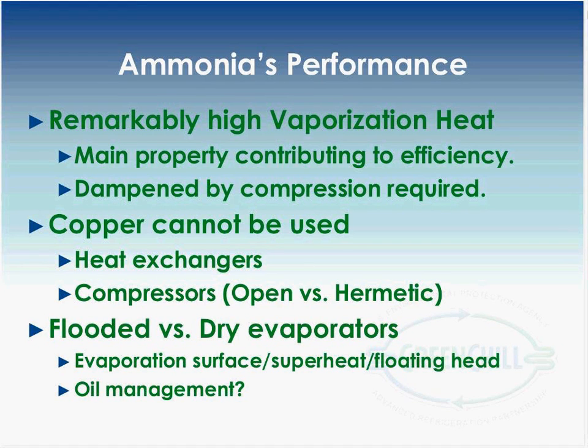Because of really low mass flow and high index of compression, there's a lot of vapor that's produced when you evaporate ammonia. So the vaporization heat of ammonia can be 9 times the vaporization heat of R12, and up to 3 times the vaporization heat of CO2, 404A, R22. Those refrigerants, you're not going to see 3 times the efficiency or 9 times the efficiency. There are factors in there, and one of them is the amount of vapor that is produced. All that has to be compressed again, so some of that's dampened by the compression required.